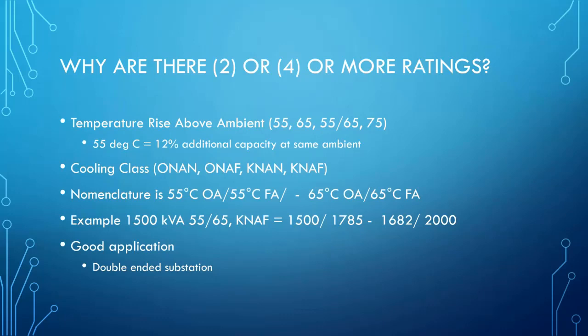In a double-ended unit sub, the transformers are usually both feeding the lineup, and the 480 volt tie breaker is open. If I'm a consultant and money is very, very important, I am going to specify a transformer that can feed one side of the lineup at its 55 degrees C non-fan rating. And I'm going to give it a dual rating and put fans on it so that if a situation arises where the transformer on side B needs to be maintained, the transformer could operate the entire lineup with the tie closed at its fan rating and its 65 degree C rating.